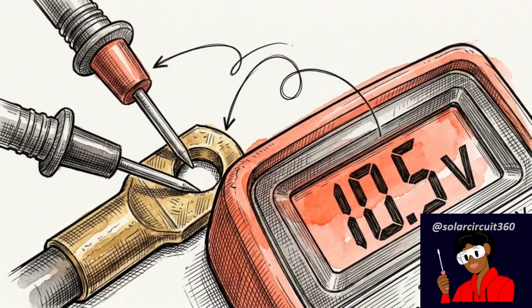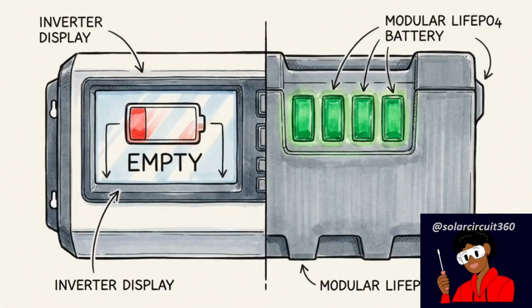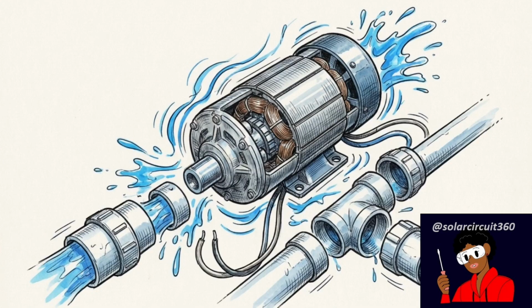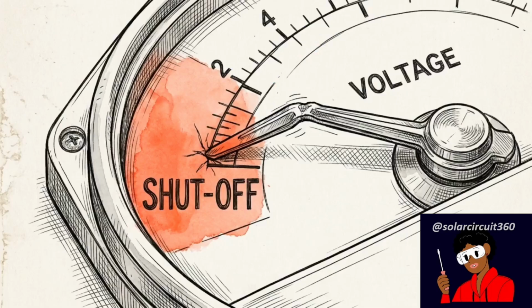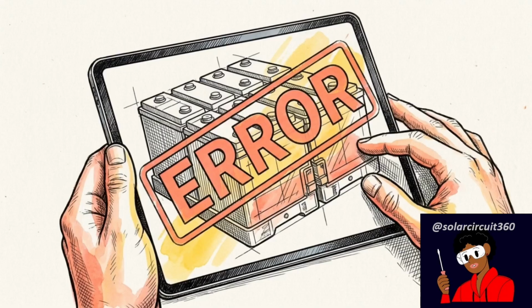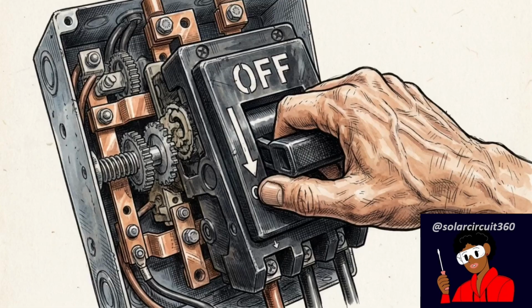This voltage drop blinds the inverter. The software reads a critically low voltage at the terminals and assumes the battery is empty, even if the cells are fully charged. Sudden power spikes, like a well pump starting, compound this by causing temporary internal cell voltage sag. This instantly drags the perceived voltage down to the emergency shutoff line. The combination of high DC current and significant voltage drop creates a false undervoltage reality. It tricks the internal systems into executing a hard crash long before the actual capacity is depleted.